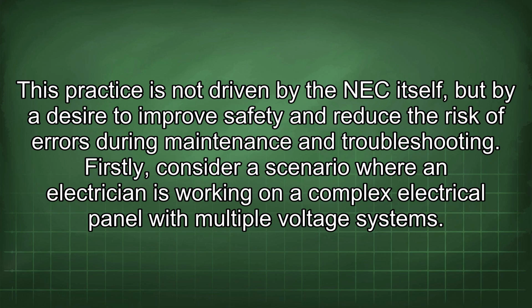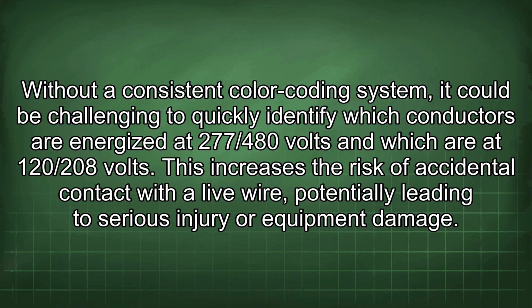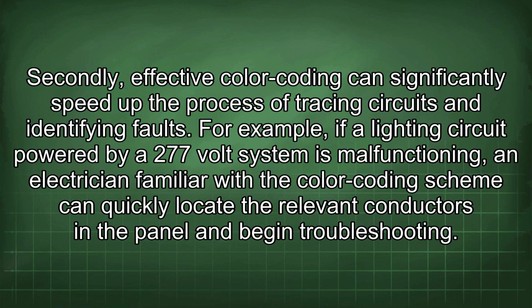Firstly, consider a scenario where an electrician is working on a complex electrical panel with multiple voltage systems. Without a consistent color coding system, it could be challenging to quickly identify which conductors are energized at 277/480 volts and which are at 120/208 volts. This increases the risk of accidental contact with a live wire, potentially leading to serious injury or equipment damage. Secondly, effective color coding can significantly speed up the process of tracing circuits and identifying faults. For example, if a lighting circuit powered by a 277-volt system is malfunctioning, an electrician familiar with the color coding scheme can quickly locate the relevant conductors in a panel and begin troubleshooting.